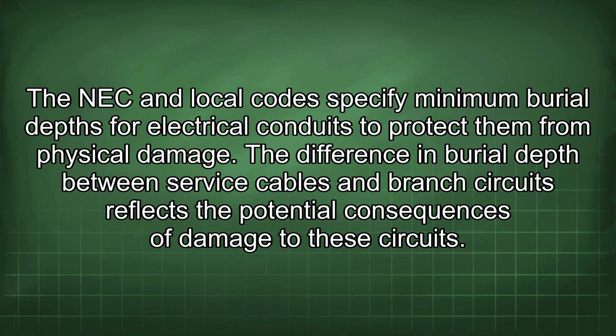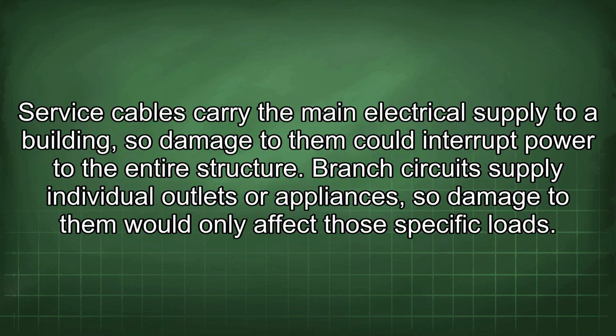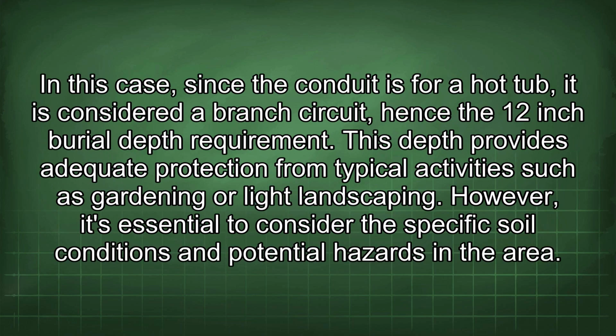The NEC and local codes specify minimum burial depths for electrical conduits to protect them from physical damage. The difference in burial depth between service cables and branch circuits reflects the potential consequences of damage to these circuits. Service cables carry the main electrical supply to a building, so damage to them could interrupt power to the entire structure. Branch circuits supply individual outlets or appliances, so damage to them would only affect those specific loads. In this case, since the conduit is for a hot tub, it is considered a branch circuit, hence the 12-inch burial depth requirement. This depth provides adequate protection from typical activities such as gardening or light landscaping.